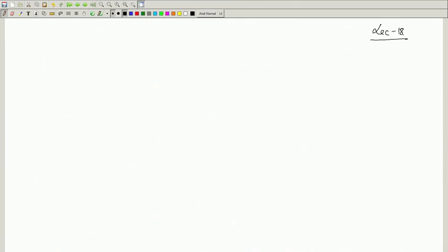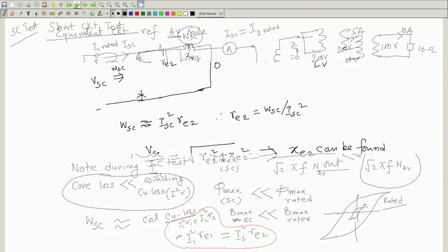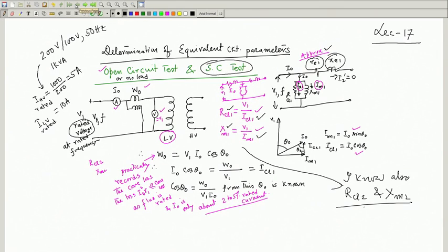Welcome to lecture number 18. We have been discussing two simple tests; by performing those two tests, one can determine the equivalent circuit of a transformer. First, you do the open circuit test, which is carried out from the LV side. If you call the LV side as side 1, then you will get RCL1 and XM1.